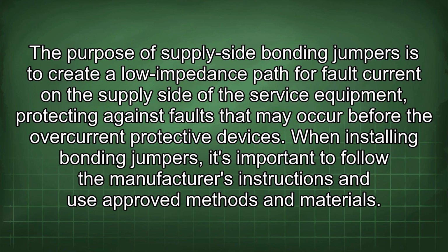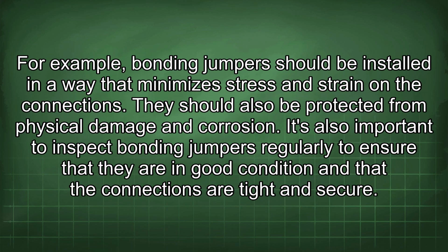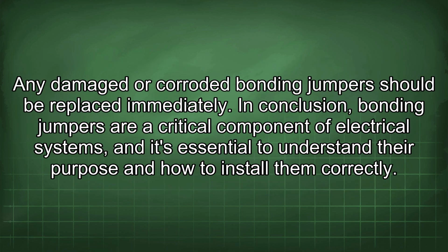When installing bonding jumpers, it's important to follow the manufacturer's instructions and use approved methods and materials. For example, bonding jumpers should be installed in a way that minimizes stress and strain on the connections. They should also be protected from physical damage and corrosion. It's also important to inspect bonding jumpers regularly to ensure that they are in good condition and that the connections are tight and secure. Any damaged or corroded bonding jumpers should be replaced immediately.